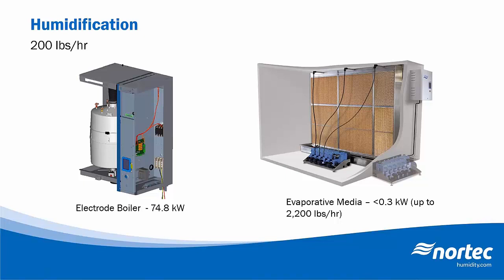So the evaporative process can actually provide two benefits for a data center. The first is, of course, reduced mechanical cooling load from the free cooling effect. And the second is the addition of humidity to help reduce ESD-induced failures. So if we talk about humidification requirements in a data center, in order to minimize ESD-induced failures, this is traditionally done using electrode-style boilers to generate steam for humidification. These can be either standalone units or small canister units installed in CRAC units. But in these types of systems, we're effectively putting energy into the system in the form of electricity to boil water. So these can consume quite a lot of electricity, and even with Title 24 in California now, they actually restrict the use of non-adiabatic humidification systems in data centers depending on the cooling or the IT loads.